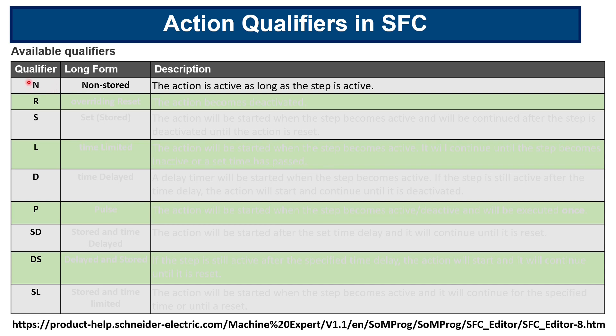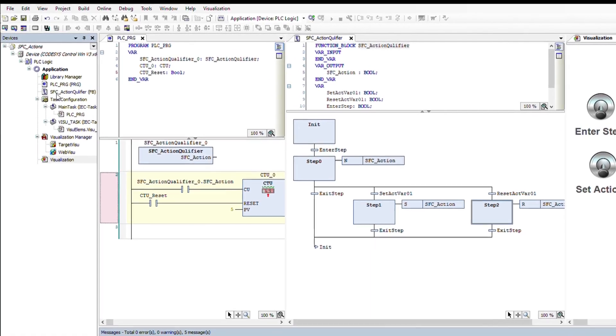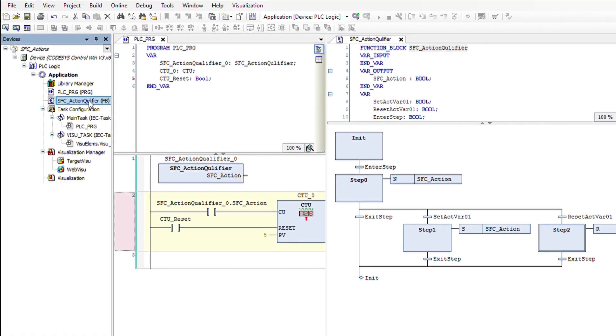Let's start with the first and simplest one, N, which stands for non-stored. The action is active as long as the step is active. So now let's switch to Codesys and I will show you how it works. Here I have a simple project. I have created a function block and called it SFC_action_qualifier.